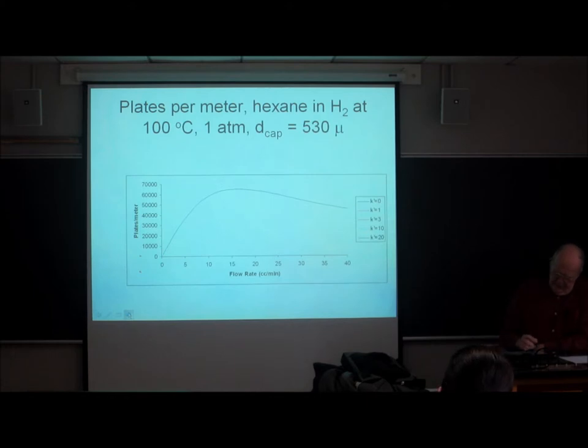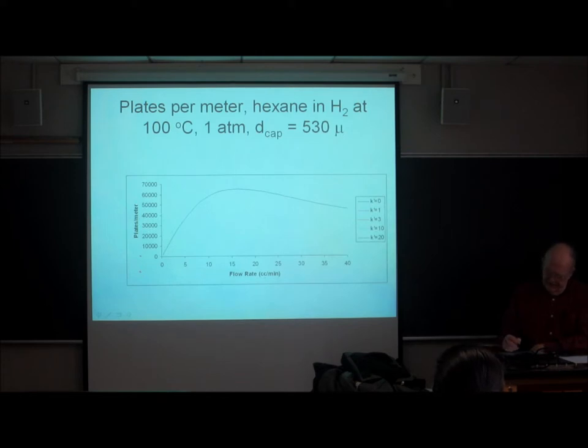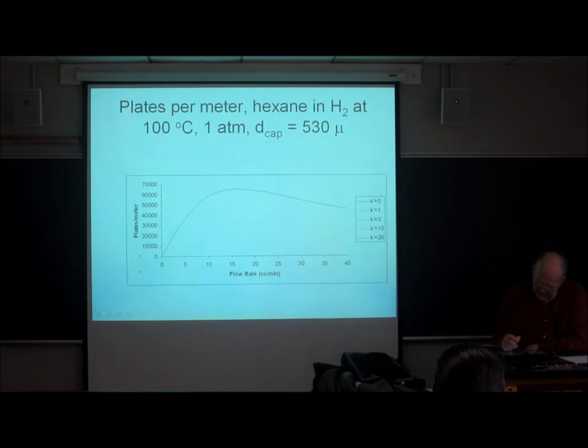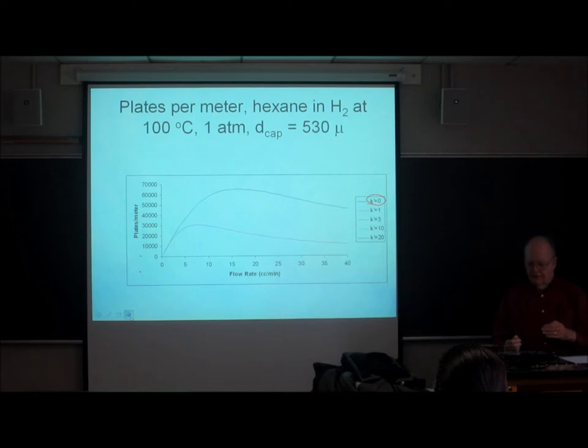We were looking at the effect of all of the broadening terms, both in terms of the HETP and the corresponding plate count. This is what the number of plates per meter looks like as a function of flow rate on this particular column. We get our best result with K prime of zero, and as we increase K prime, the plates per meter drops a lot.